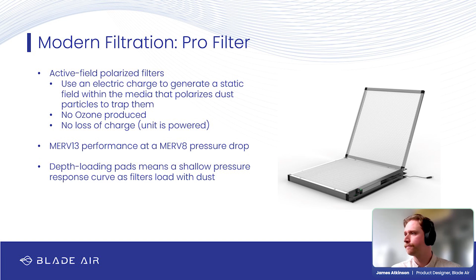We don't do that because we're charging the entire pad. Every single filter fiber has surface area that can trap dust. So you have much more room to trap dust without getting that associated pressure rise. So it really solves that problem, right? We've now decoupled the filtration performance from the pressure drop. We have a MERV 13 performance at a pressure drop close to a MERV 8.